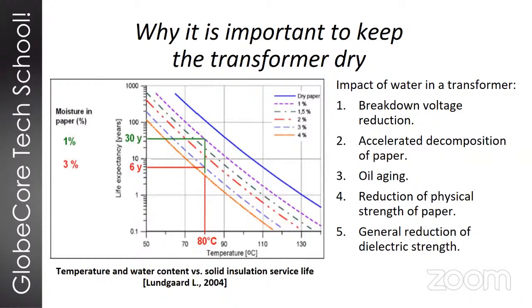But if the transformer works at the same 80 degrees Celsius, but with humidity in the paper of about 3%, and its life expectancy is just 6 years. And so using this data, we can obviously see the necessity of continuous monitoring and control of moisture in our equipment to prevent any increase that may happen due to internal or external processes and influences in the transformer.